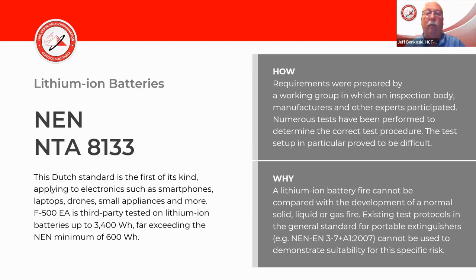This test goes up to a 600 watt-hour battery. We take 6 batteries, 100 watt-hours each, and set them on fire. When they go into thermal runaway, extinguishing takes place, and the batteries need to be extinguished. Once extinguished, they have to sit for 20 minutes with no reignition. At the end of that time, they check for an electrical charge on the batteries, to make certain they didn't completely burn up, that you did extinguish them and they didn't just burn themselves out. So we check to make sure the batteries still have a charge.